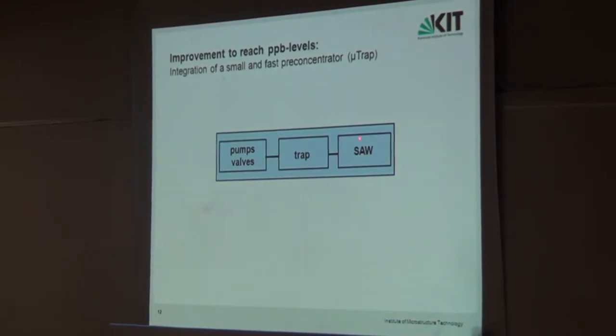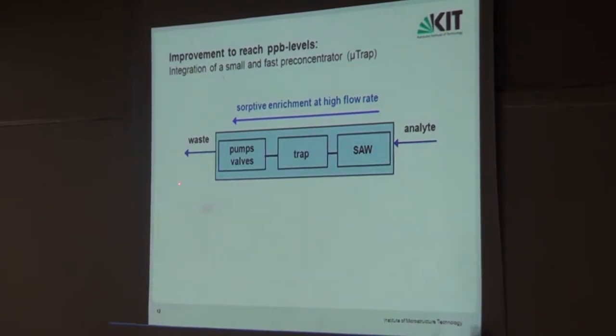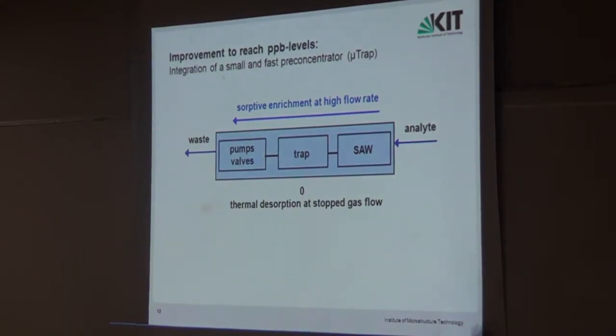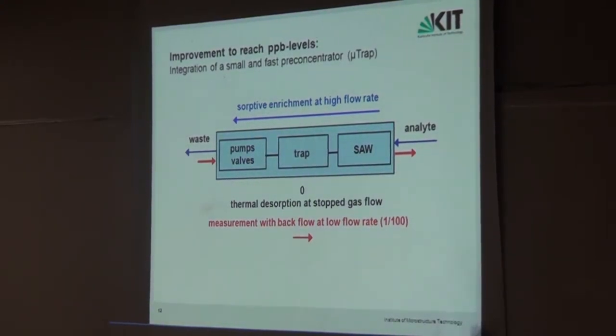The SAW sensor array is on one side; on the other are the trap and a system of pumps and valves. We aspirate with a pump at high flow rate, the analyte over the whole system. We zero the SAW sensors on the non-enriched analyte, and in one cycle blow one liter of gas through the system. Then we stop the flow, stop the pump, and heat up the trap. The trap material — for instance Tenax — absorbs the analyte and releases it when heated. We then blow it back at a very small flow rate — 1/100 of the original — over the sensor.